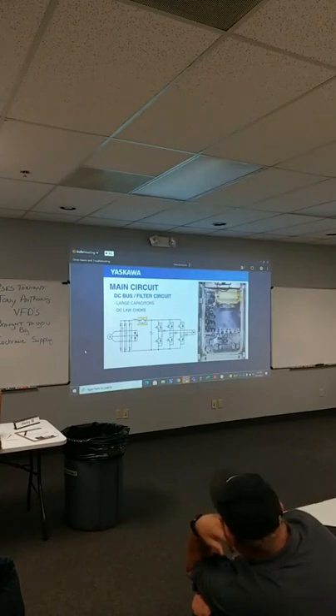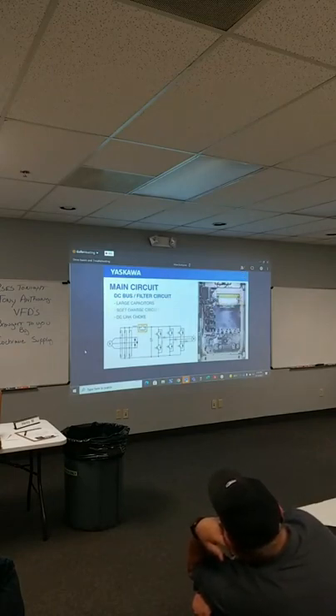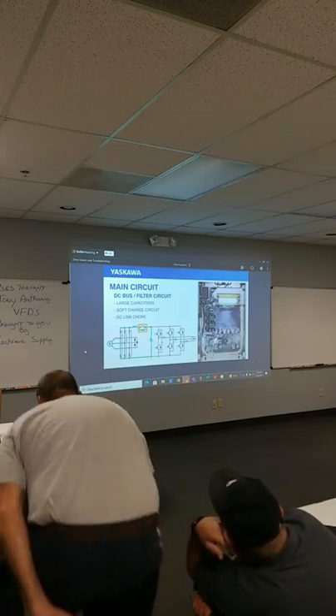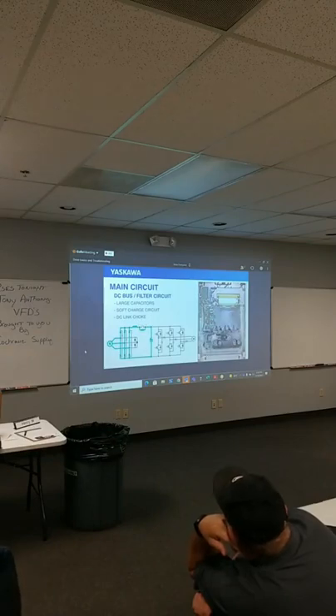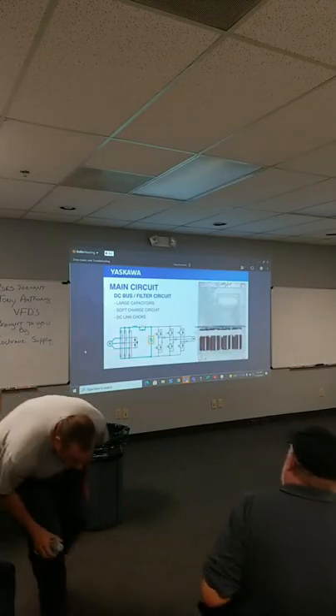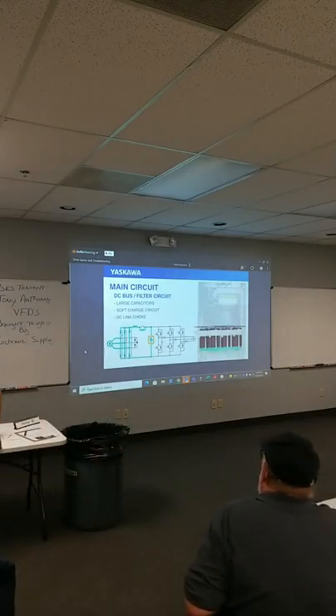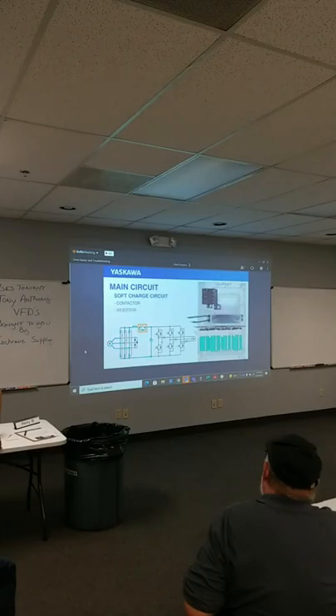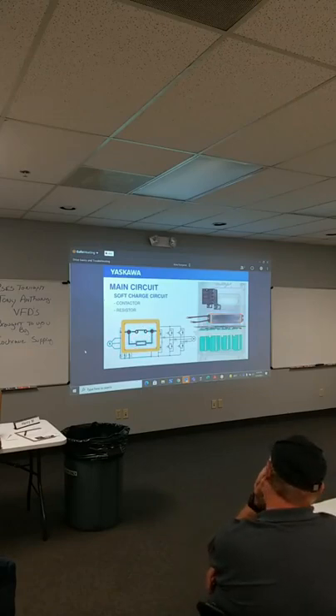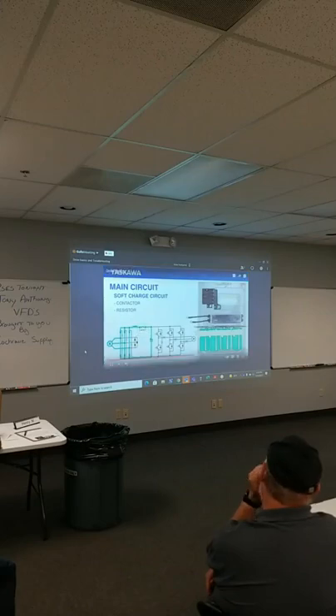The components between the rectifier and the filter capacitors comprise a soft charge circuit. When you apply power to the drive, the unit must safely power up. This happens relatively fast, but we must slowly charge the capacitors in the drive. An uncharged capacitor will act like a short if full voltage is applied to it instantly. This is not desirable because the inrush current may be too high for the rectifier and upstream supply components. Therefore, we use a soft charge circuit to slowly charge the capacitors. The soft charge circuit is made up of a contactor and a resistor. A resistor limits the current flowing to the capacitor. After the capacitor charges, the contactor closes and bypasses the resistor. Remember, electricity, like most of us, will follow the path of least resistance.